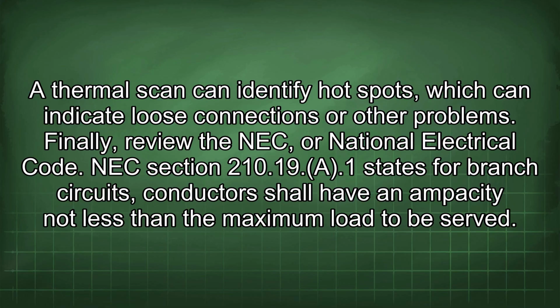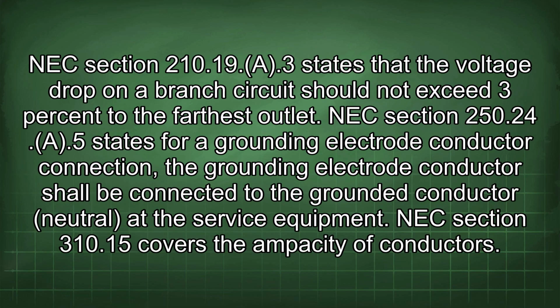Finally, review the NEC, or National Electrical Code. NEC Section 210.19(A)(1) states for branch circuits, conductors shall have an ampacity not less than the maximum load to be served. NEC Section 210.19(A)(3) states that the voltage drop on a branch circuit should not exceed 3% to the farthest outlet.